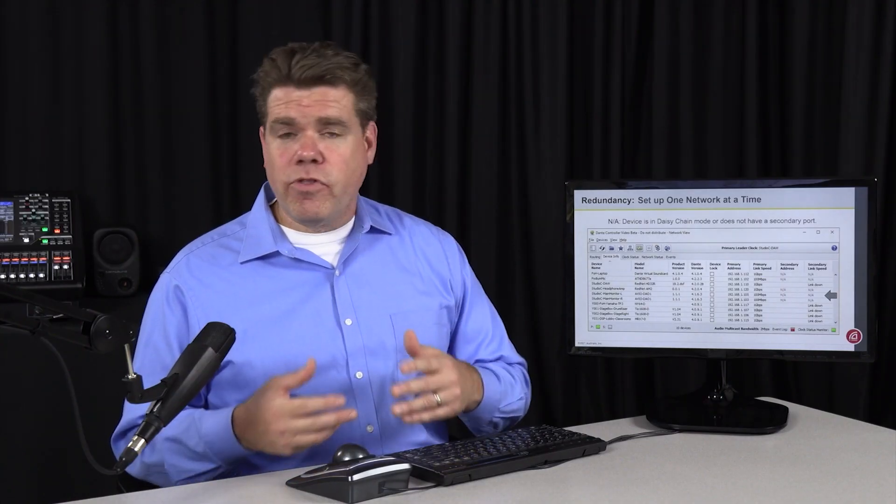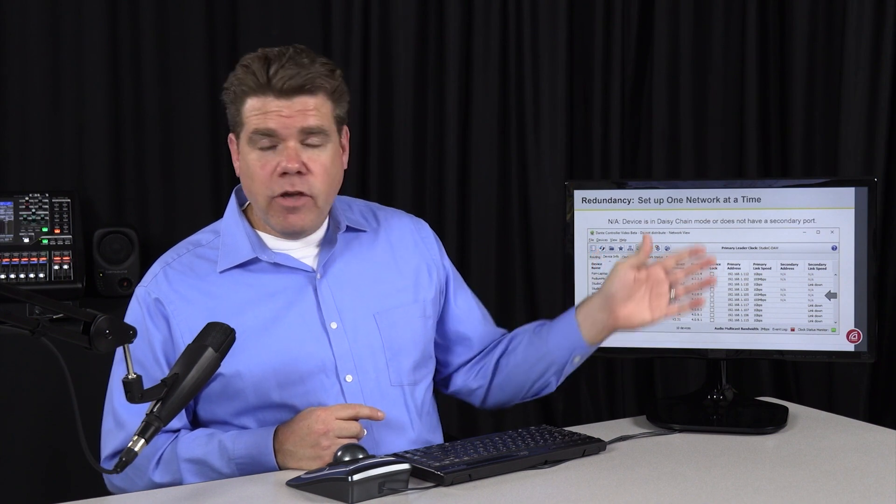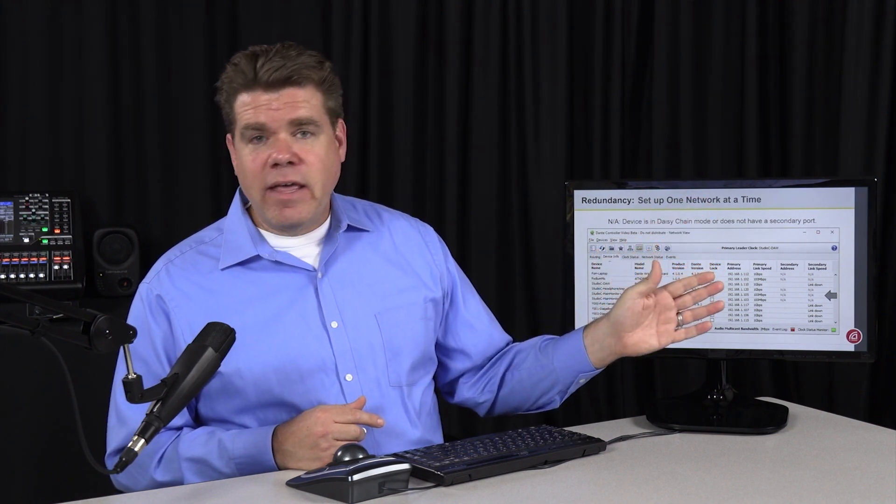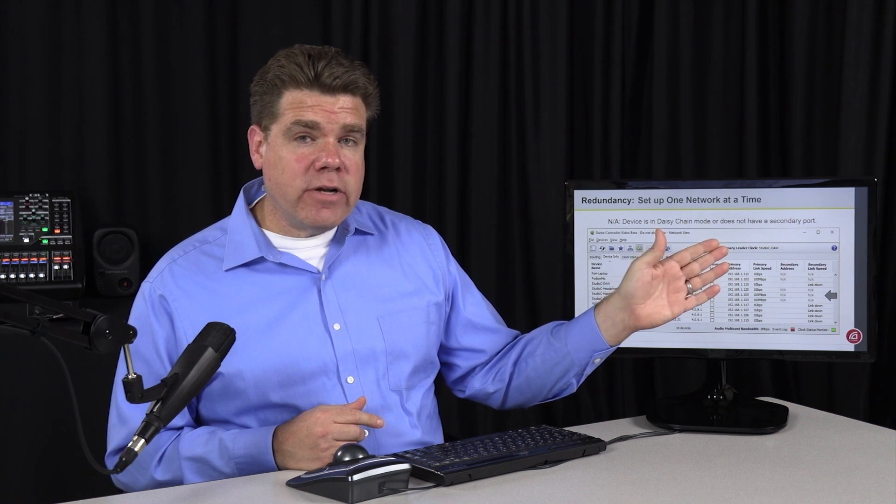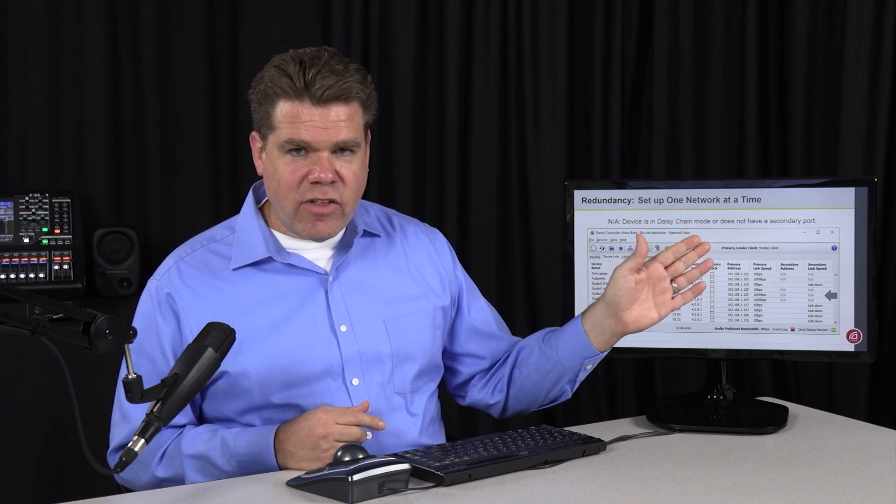So if you're commissioning a system with a redundant configuration and you've turned off your redundant network, you should be able to go down this list and anytime you see NA in that secondary port, you should be able to verify that that is a device that only exists on the primary.